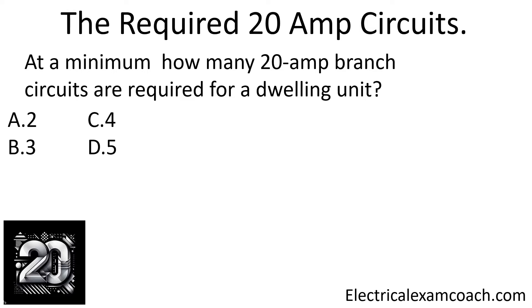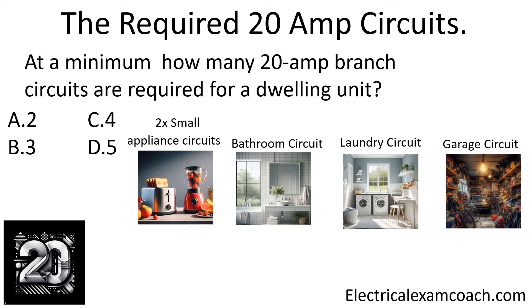At a minimum, how many 20 amp branch circuits are required for a dwelling unit? This is asking a very specific question. There is a code minimum of 20 amp branch circuits required in every dwelling unit. The correct answer is five. It's going to include our two small appliance circuits, our bathroom circuit, our laundry circuit, and our garage circuit. These are not to be confused with questions asking about general, lighting, or receptacle circuits. These are the code minimum of the required 20 amp branch circuits in a dwelling, and the answer is five.